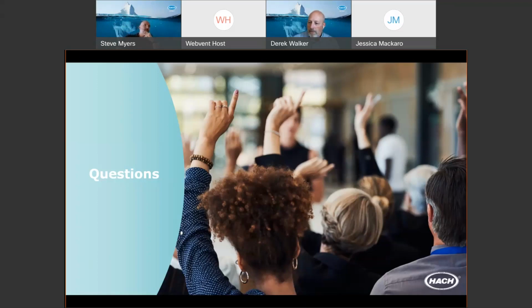It depends, like everything, there's going to be some rules of thumb. For me, in an influent environment, we're probably looking at manual wipe down on a weekly basis, and it might be something you'd want to look at even more frequently based on performance. One thing to note is when it comes to pH sensors, people can be a little sensitive about what they use to wipe down the bulb, but with an ORP sensor, a bit more aggressive elbow grease is totally okay. I'd suggest a bristle brush, not necessarily wire bristles, but a good toothbrush type of bristle brush is fine on an ORP sensor.